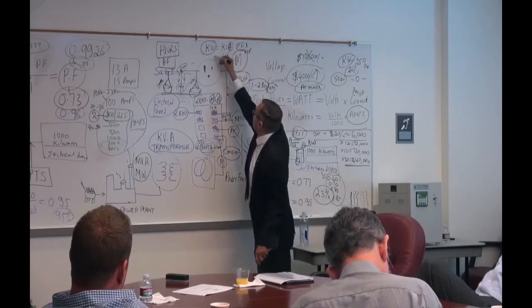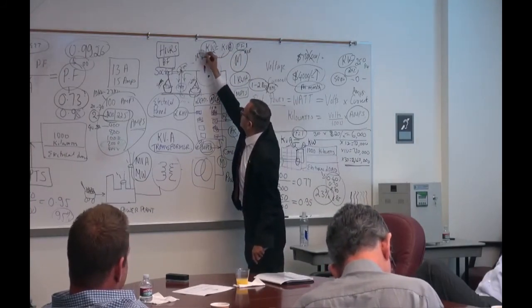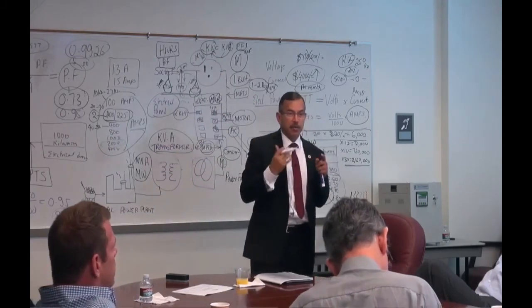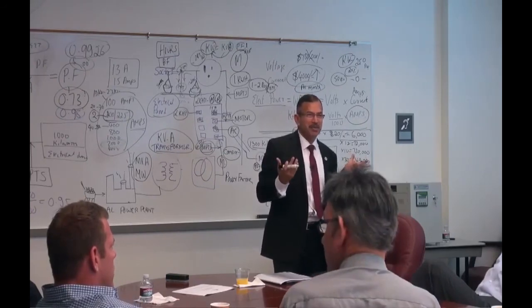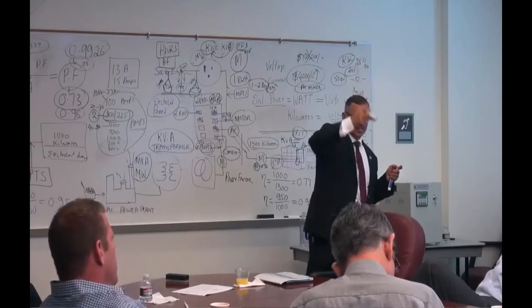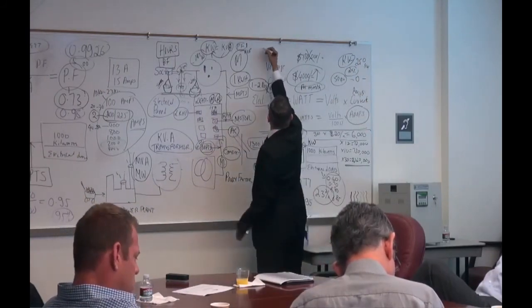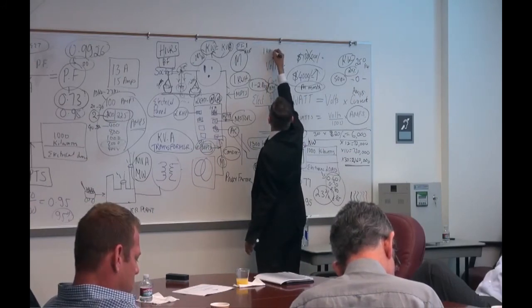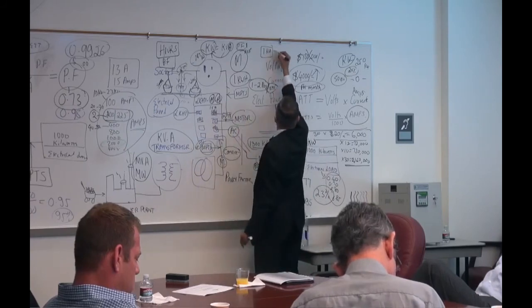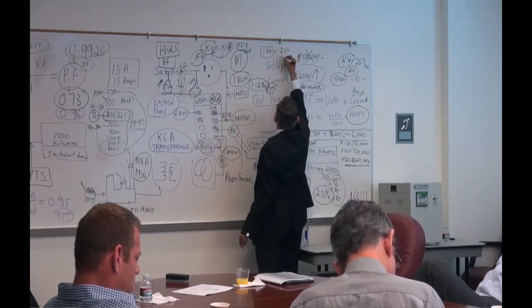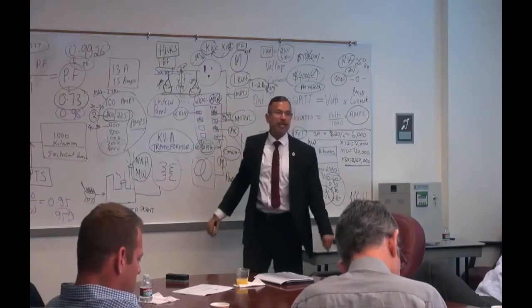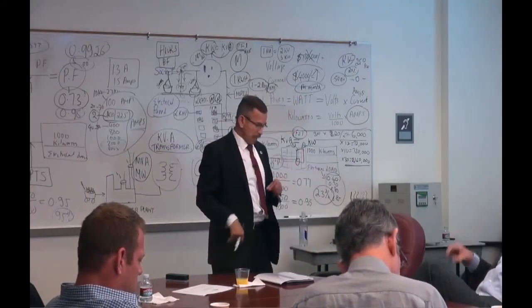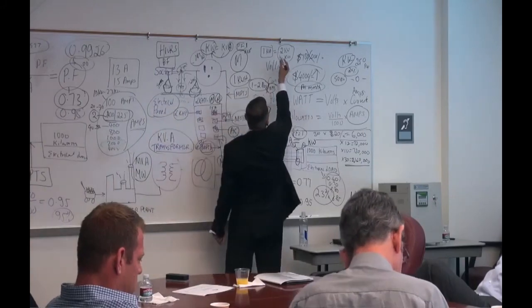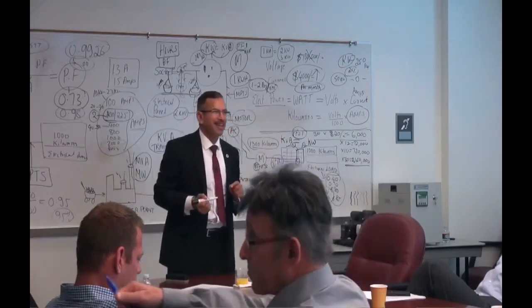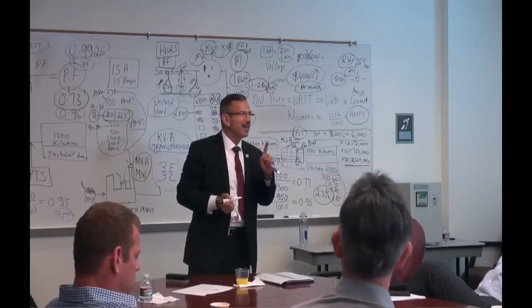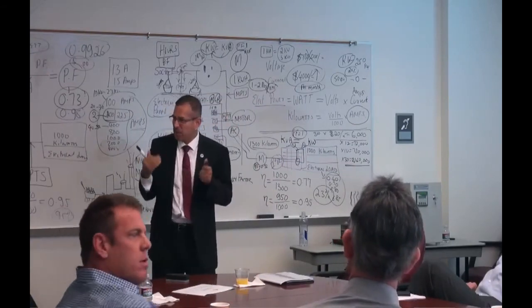Then what happens, every amp you save has a 0.83 kilowatt decrease on your bill. Realistically, your bill may be more because the utility bill is not billing you for actual consumption. They are billing you for the peak, so if you are consuming 1 kVA in our calculations, we are talking about real power, your bill could be 2 or even 3 kilowatts, because that was the spiked-up value, the highest value in a 15-minute period. So if you save 1 kVA, what is the decrease on the bill? Not 1 kVA, it is 2 or 3. So whatever we save is actual values you are going to save.